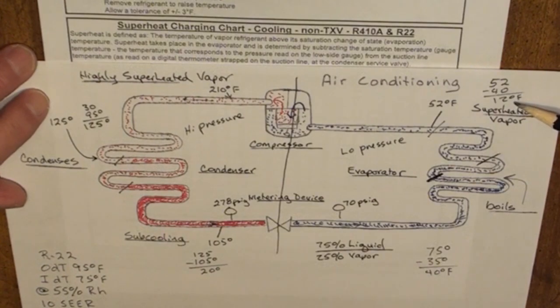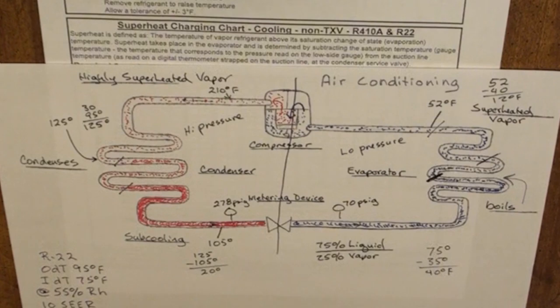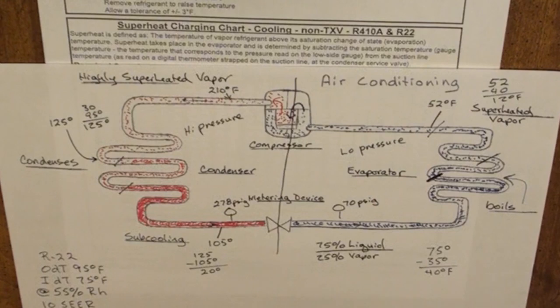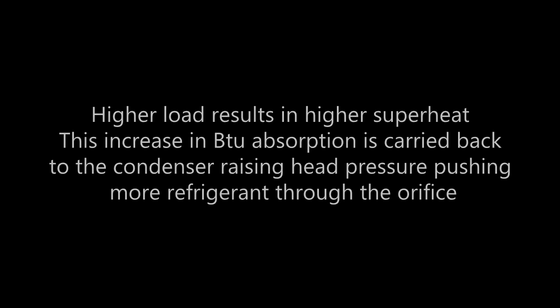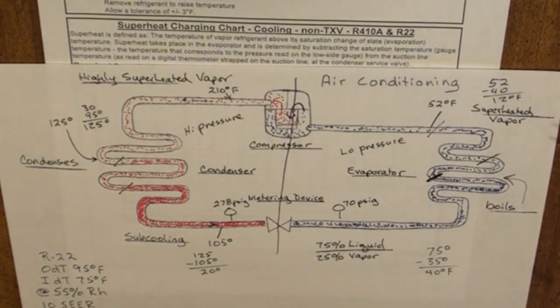Instead of 12 degrees of superheat, we may in some cases have 20 or 25. Unlike subcooling, the outdoor and indoor conditions have a much greater effect on how much refrigerant is fed to the system. In other words, a correct charge may in fact have 15, 18, 20 or more degrees of superheat.